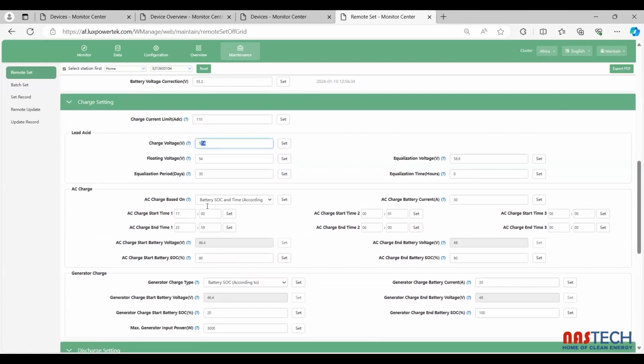Charge voltage, this is my charge voltage, 57, my float voltage. This is applicable to the lead acid equalization. So within the 30 days period, it will check my batteries, charge my batteries up to the equalization voltage of 58, and it will equalize your battery at 58 volts again. And then obviously, in your normal operation, the battery will come down from that 58 and be within the 54 to 55 range. And then it will charge at 57 and float voltage of 54.